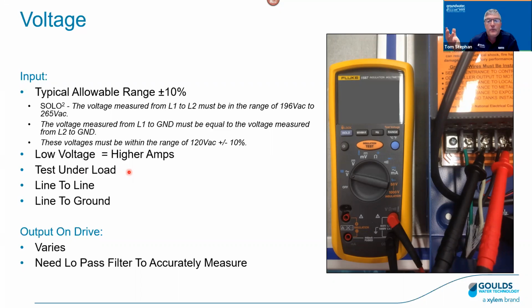And for example, like 230, we're going to test line to line and line to ground. Line to ground is going to be half that of line to line in the 230 system. And also just note that on a drive, the output does vary. So if you go to measure the output voltage and it is running, you are going to see that change. But you can measure that. If you do measure that, it's recommended to have this type of meter here that has a low pass filter, that little guy right there.